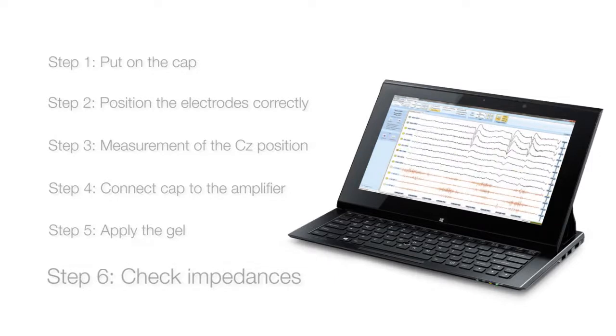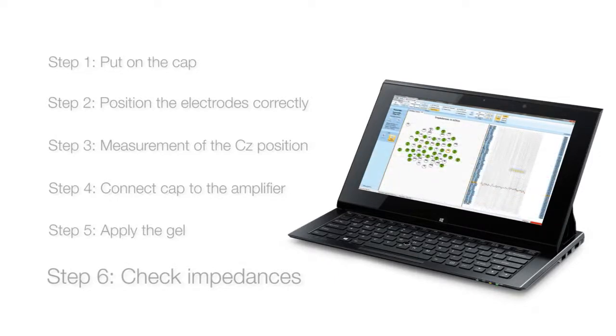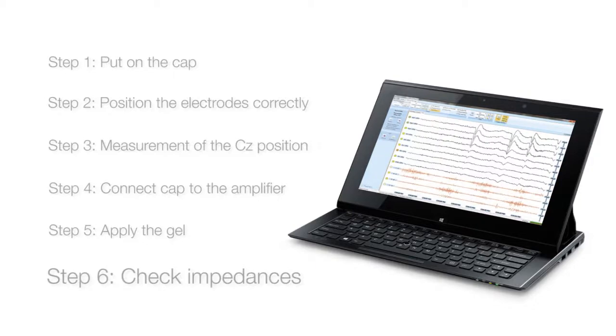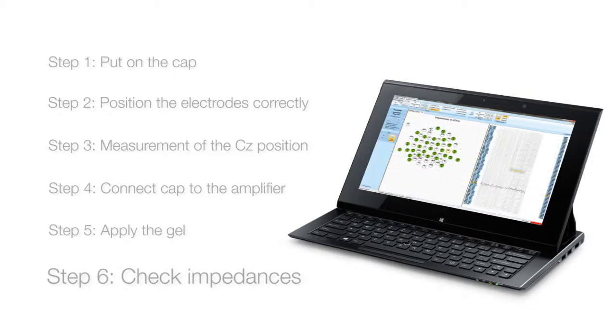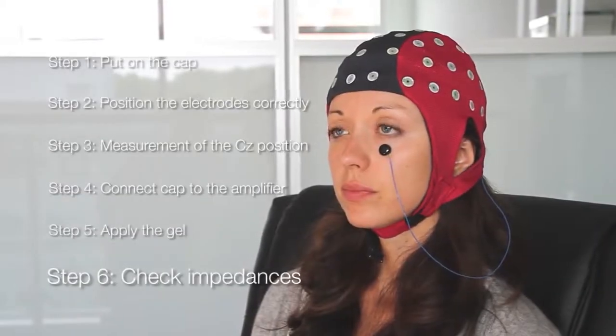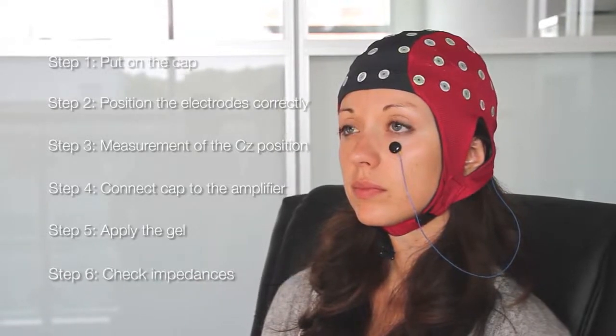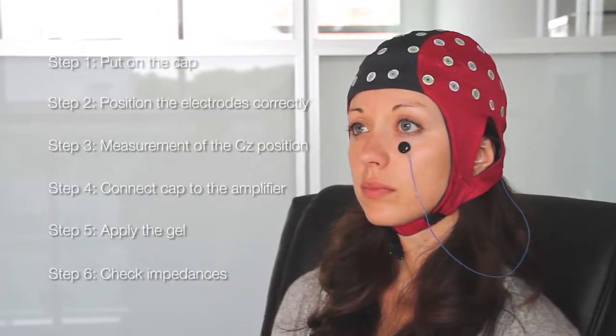It may be helpful to switch between the impedance check mode of your EEG system and the signal display mode while confirming that the connection is satisfactory. As a simple test of quality, you can ask the patient to open and close their eyes and to move their hand.